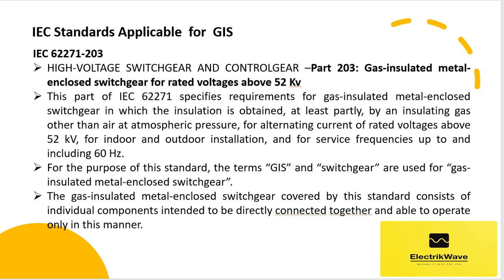IEC 62271-203: High Voltage Switchgear and Control Gear, Part 203, Gas Insulated Metal Enclosed Switchgear for Rated Voltages Above 52 kV. This part of IEC 62271 specifies requirements for gas-insulated metal-enclosed switchgear in which the insulation is obtained, at least partly, by an insulating gas other than air at atmospheric pressure, for alternating current of rated voltages above 52 kV, for indoor and outdoor installation, and for service frequencies up to and including 60 Hz. For the purpose of this standard, the terms GIS and Switchgear are used for gas-insulated metal-enclosed switchgear. The gas-insulated metal-enclosed switchgear covered by this standard consists of individual components intended to be directly connected together and able to operate only in this manner.